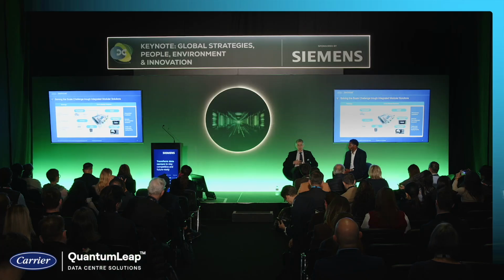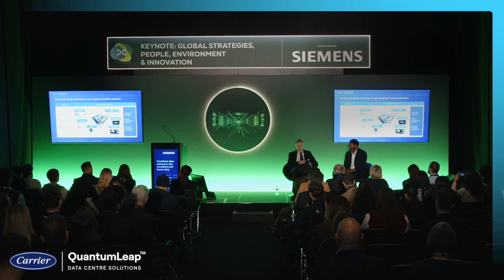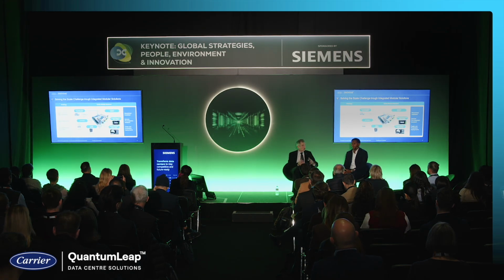And basically, it's like a human body. You have several elements - chiller, air handlers, CDUs, pumps, controls - and you can silo them, slice them into different elements, and what I call lose synergies between elements. You will not optimize the overall system, which depends on ambient conditions and loads, etc.